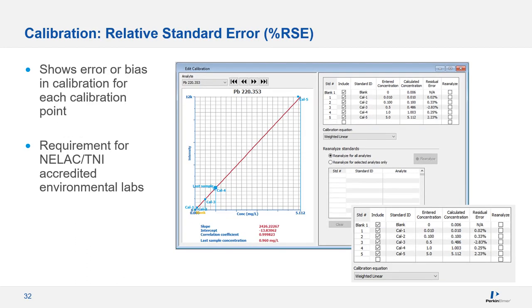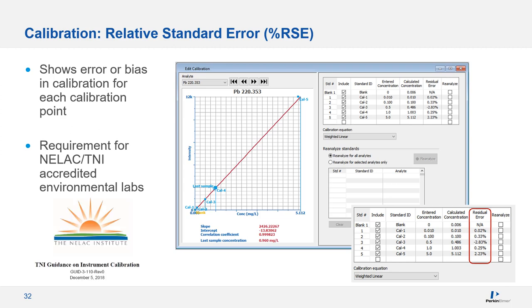Unlike R-squared, relative standard error, or residual error, is an actual statistical measure of the error or bias in each calibration point. It's a reporting requirement for all NELAC and TNI accredited laboratories. A %RSE closer to zero indicates less error or bias in your calibration.